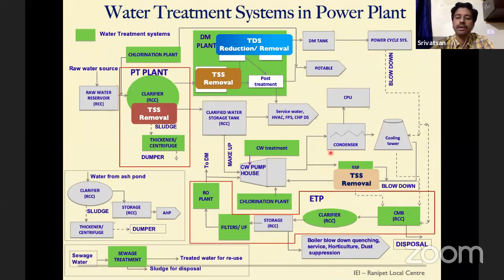Here, there are a lot of dust particles suspended in the atmosphere in a thermal power plant. So these get accumulated in the cooling water forebay. To remove these suspended particles, we have a TSS removal system called side stream filtration. Then there is a conditioning requirement for this cooling water cycle, because we are recycling this water in the cooling water system to minimize water wastage. Then we have suspended solids removal.